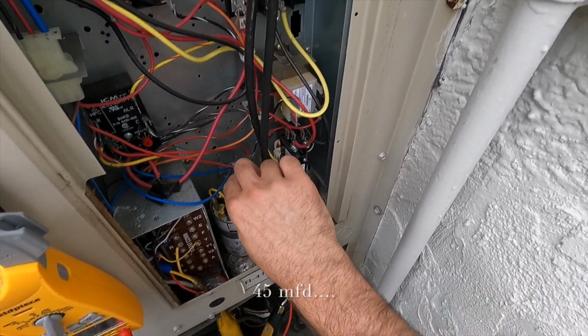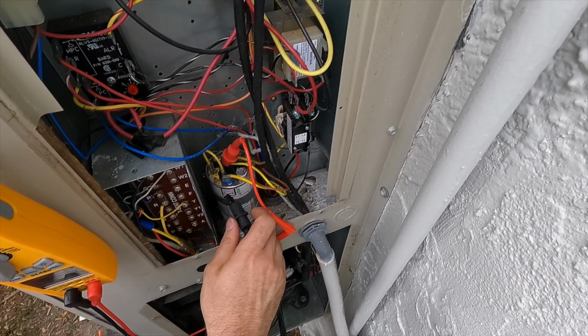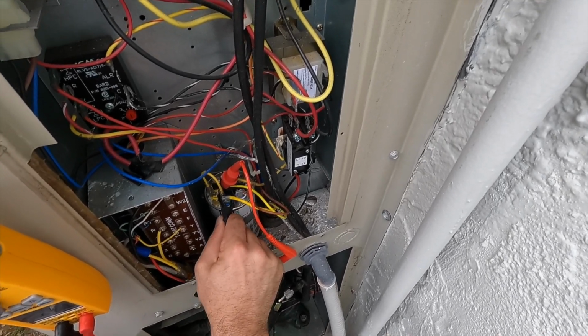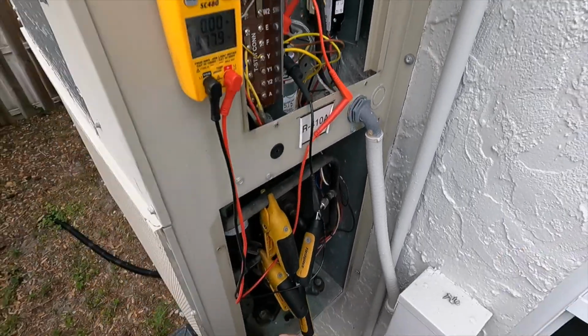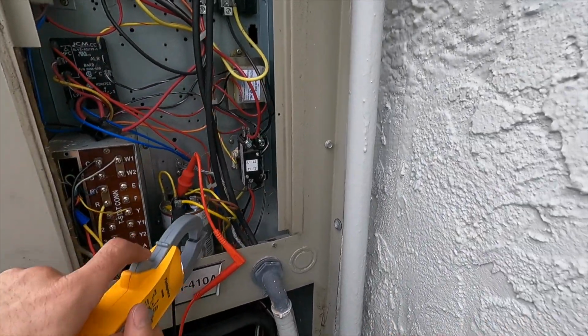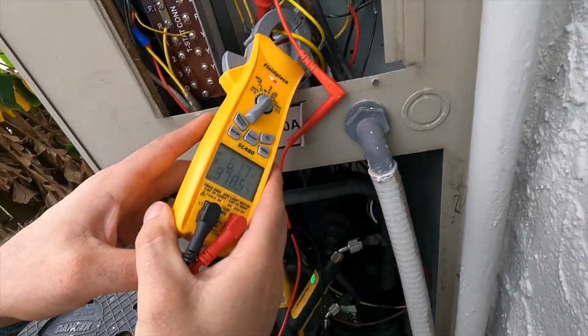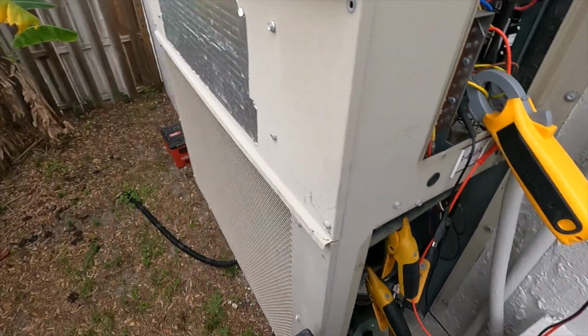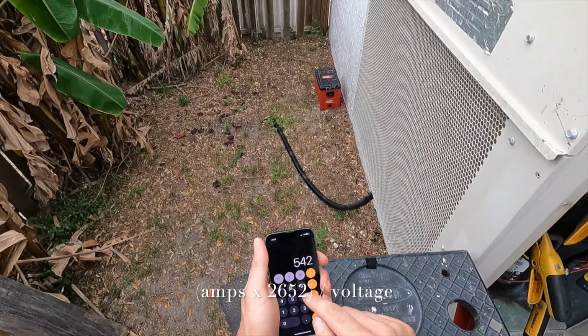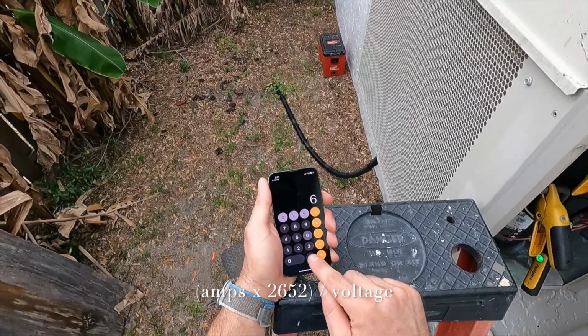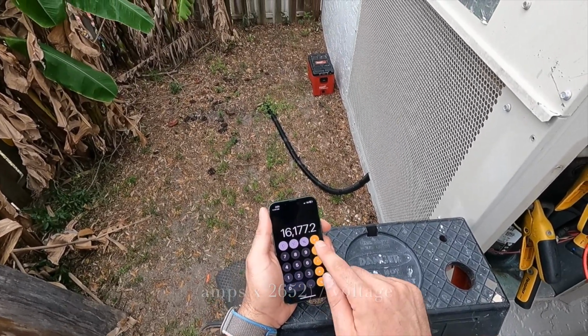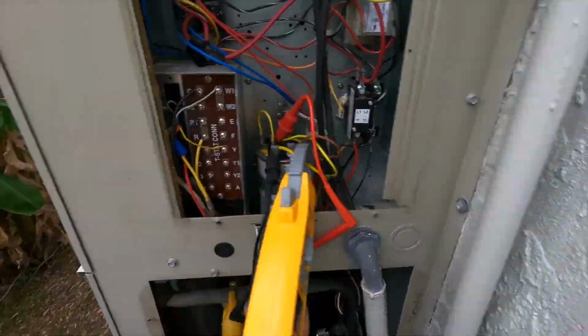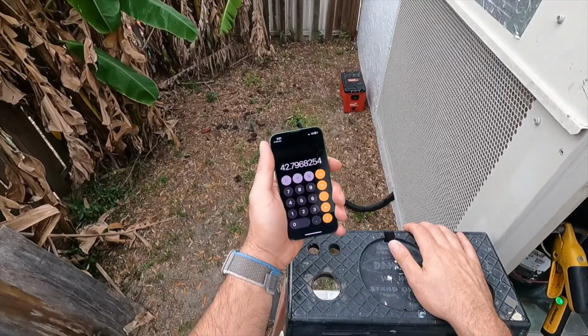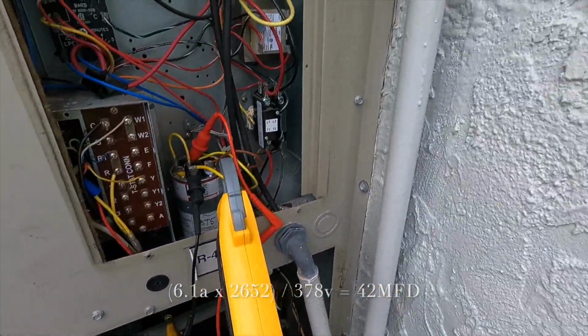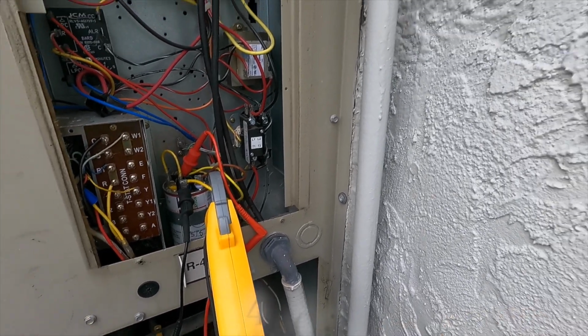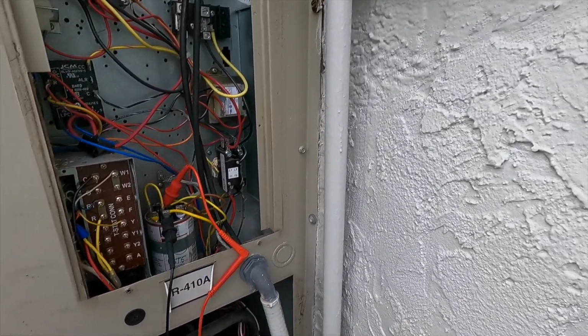So we're going to do this under load. We're going to go ahead and put one of my gator clips here, another gator clip here, check our voltage, and then we're going to take that amp draw off of the same wire. 6.1. So we're going to go ahead and do a little calculation here. 6.1 times 2652 divided by our voltage, and that's going to give us our under load microfarad, 42. So we got a 40 microfarad capacitor for a compressor, so it is working. It also looks new, so I didn't really have any doubts on that.